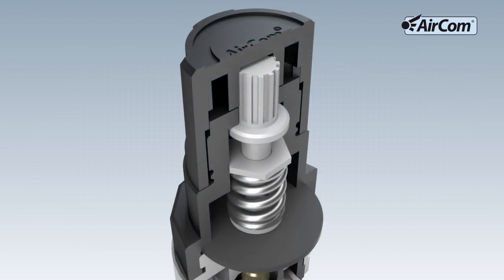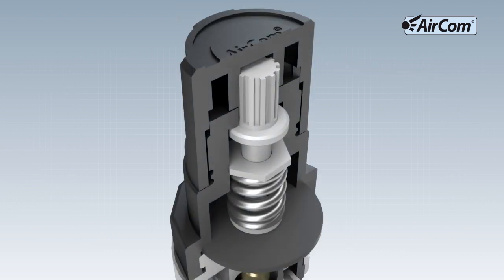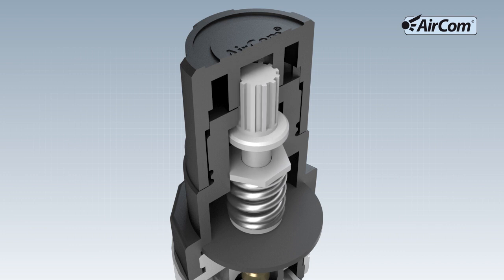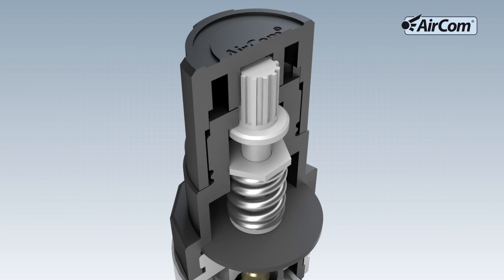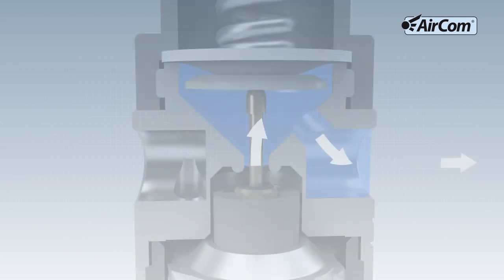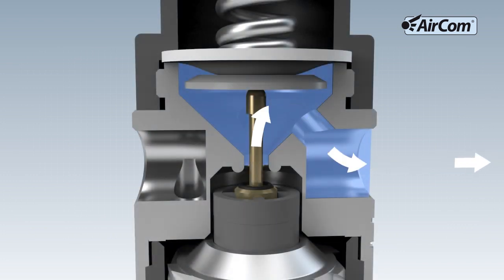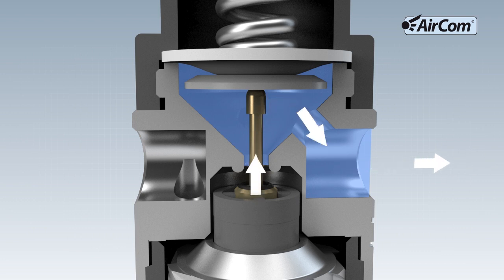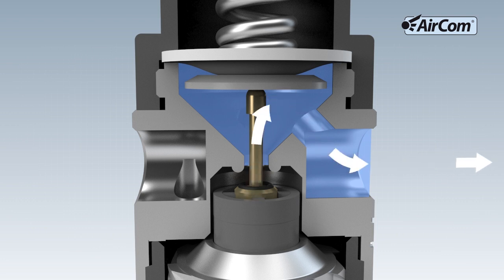By turning the adjusting knob clockwise, the range spring is pre-tensioned, the tappet is pressed downward and the valve seat is opened. This sets the output pressure set value. The compressed air flows from the input through the filter part and the open tappet to the output, shown here in light blue.